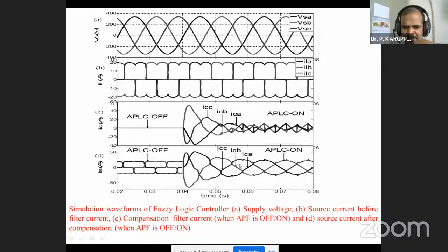This is the active power filter total harmonic distortion measured without the active power filter and with the active power filter. With the active power filter, you can see it is reduced to 3.47. And this is another load under steady state and transient state - we took the order of harmonics, and here we are getting the voltage and current that maintain unity power factor.